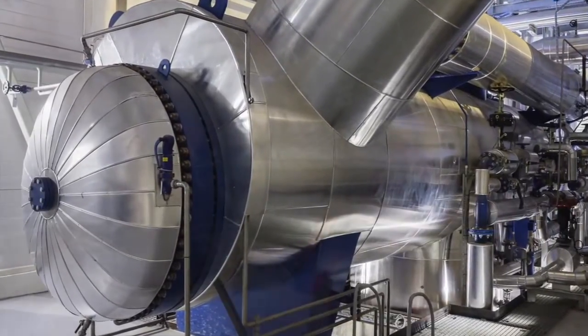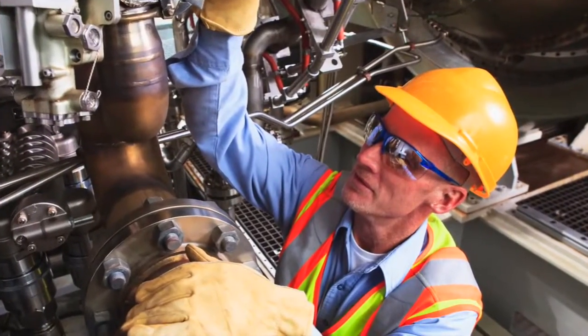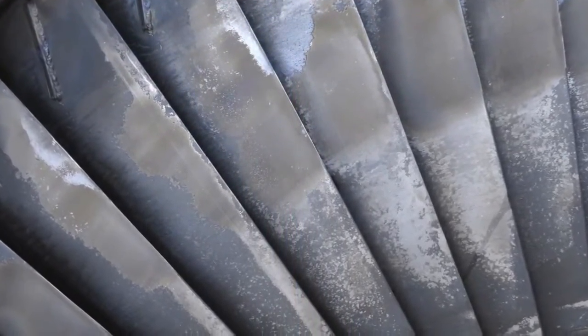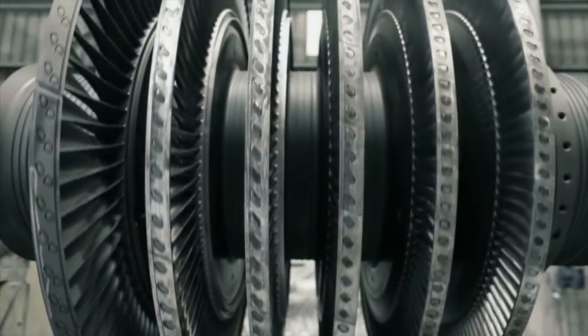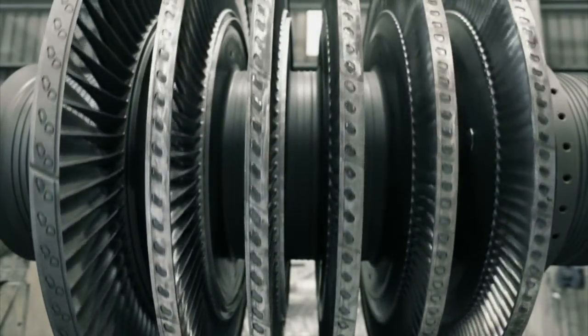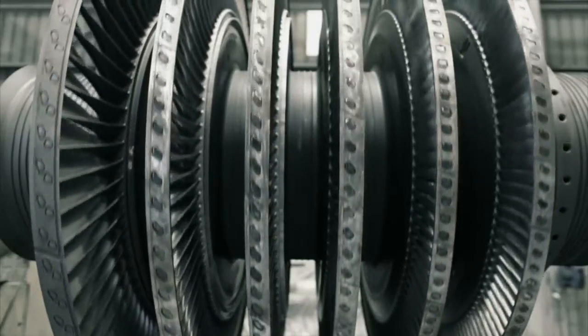More importantly, such corrosion has a significant impact on a power plant's safety. To reduce the risk of damage from chlorides and sulfates, they are routinely specified at less than 2 ppb levels as part of cycle chemistry guidelines and turbine warranty requirements.